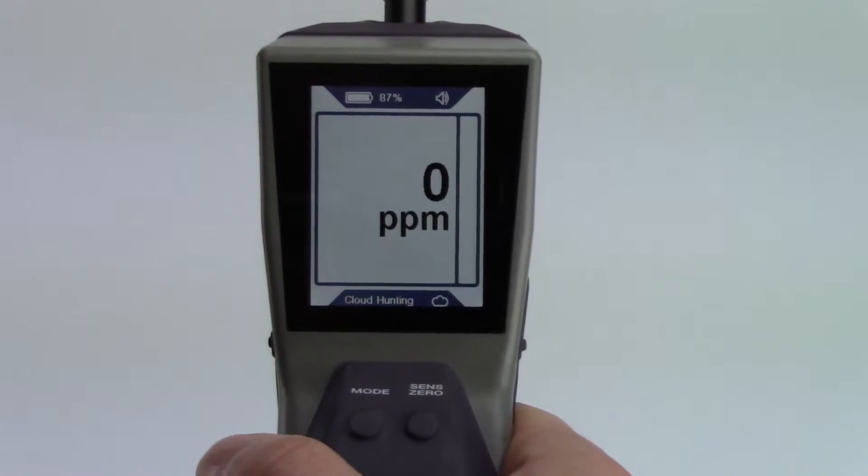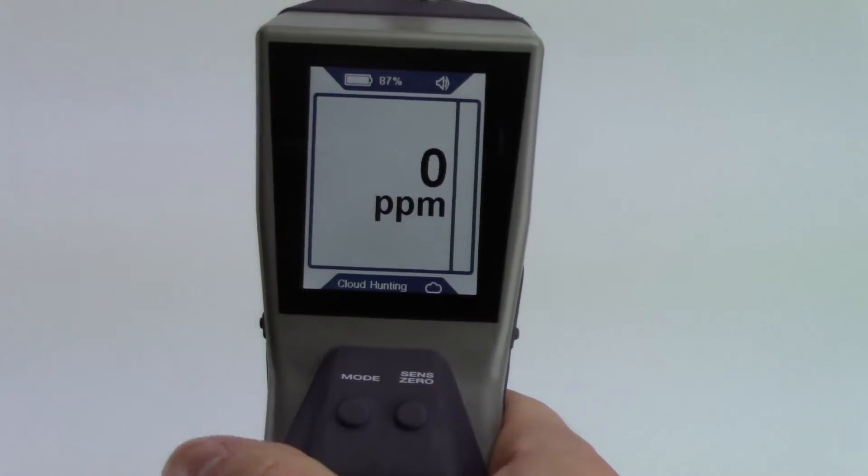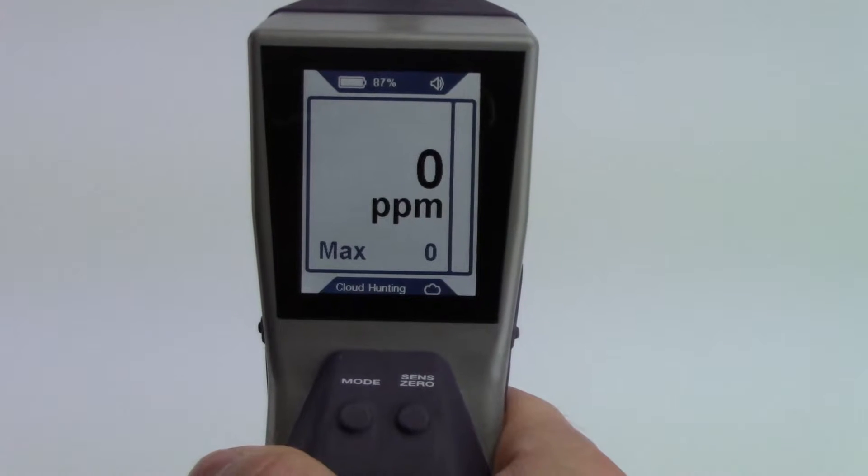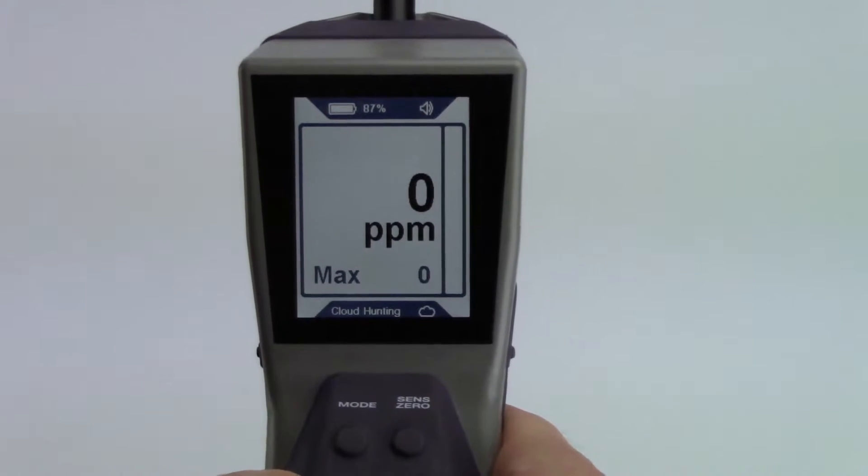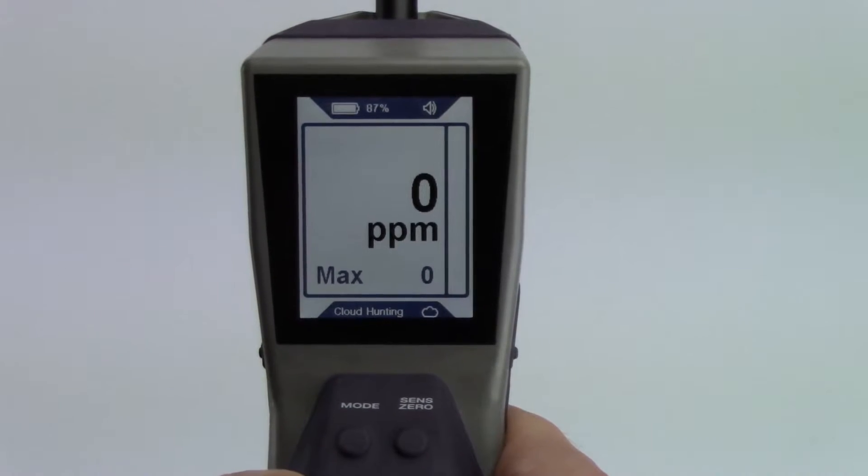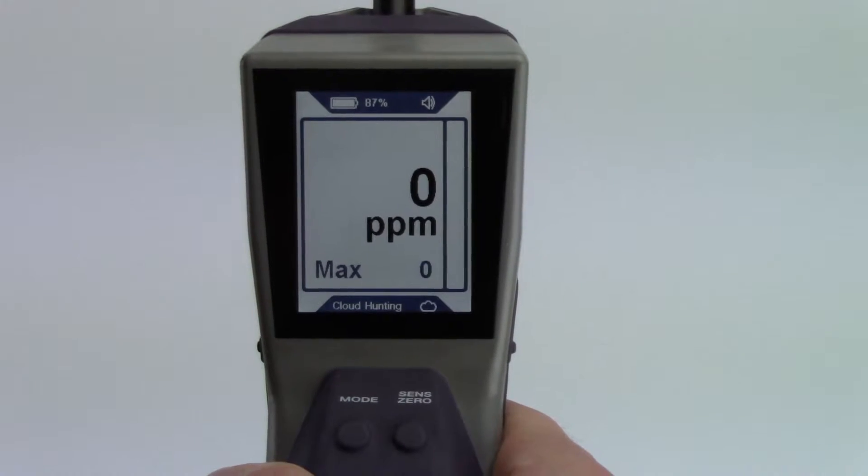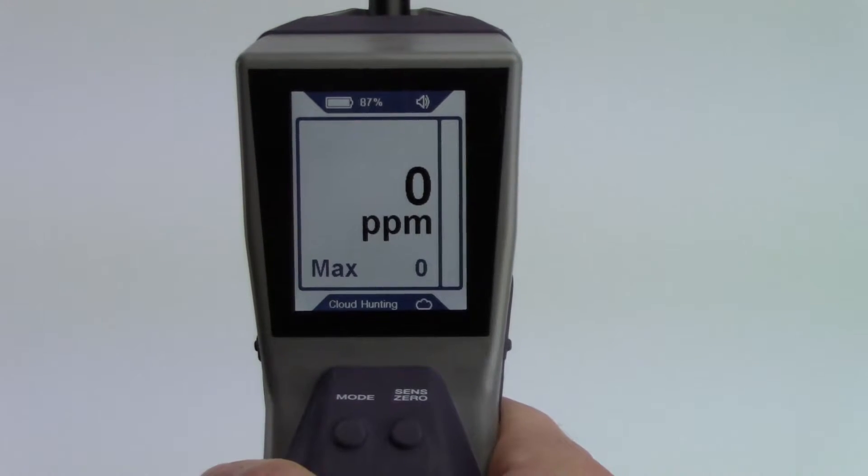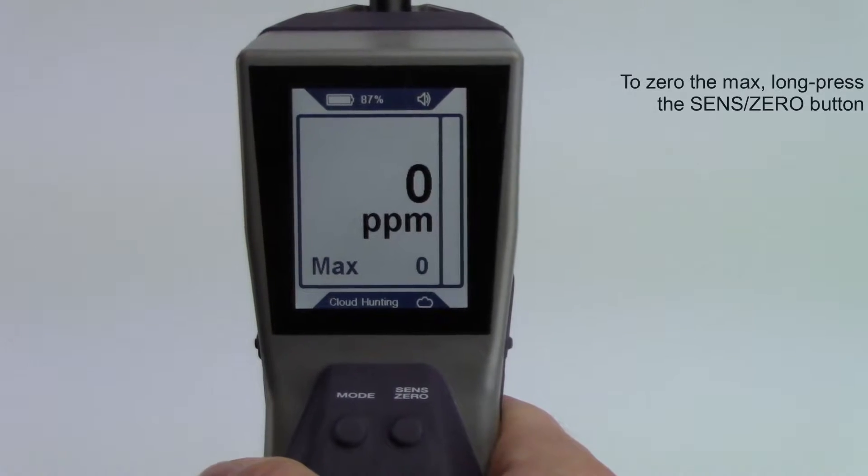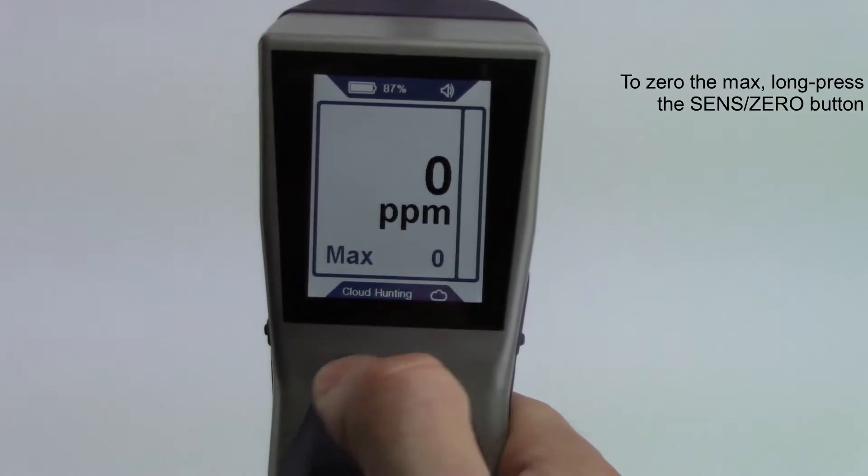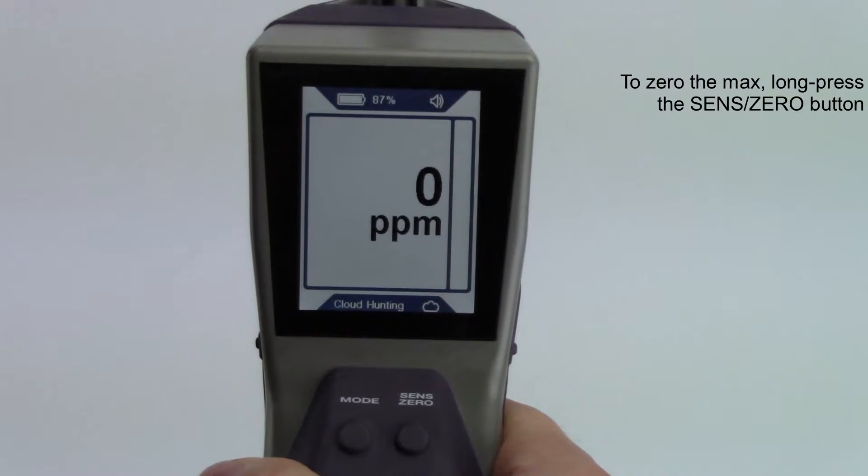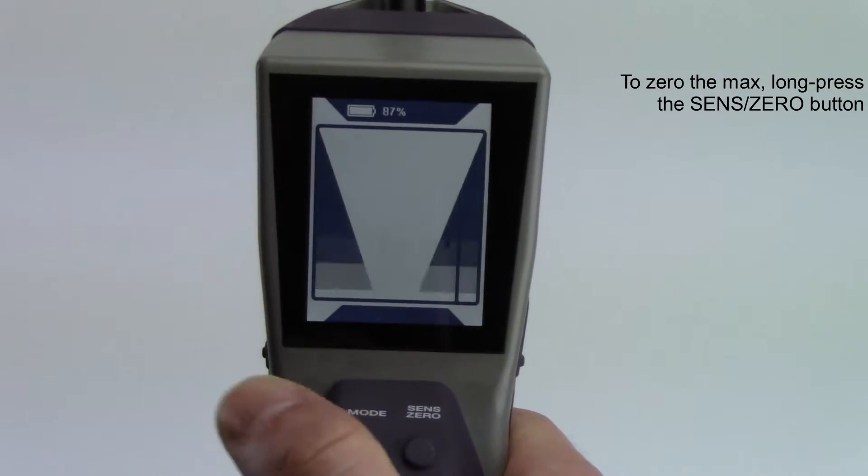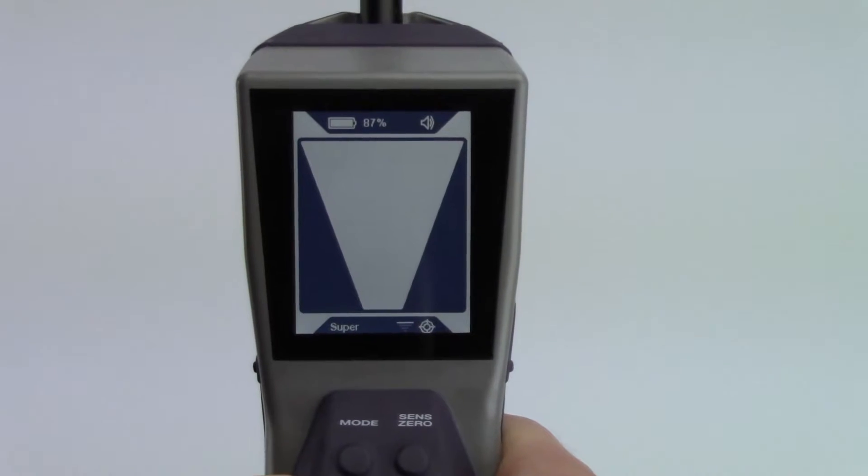Pressing the Sens/Zero button will enable or disable the Max Hold feature. This displays the highest PPM reading DTEK Stratus has detected. When the general area is found, switching to pinpoint mode will help accurately identify the exact leak location.